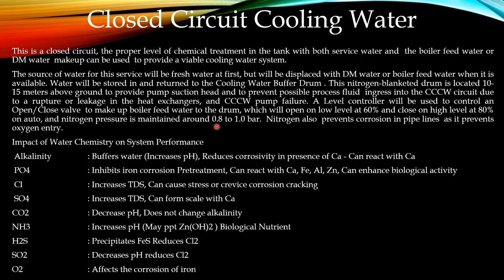Nitrogen pressure is maintained at around 0.8 to 1 bar. Nitrogen also prevents corrosion in the pipeline and prevents oxygen entry. The impact of water chemistry on system performance: alkalinity in water buffers the water, which will increase the pH and reduce corrosivity. In the presence of calcium, it will react with calcium salts.